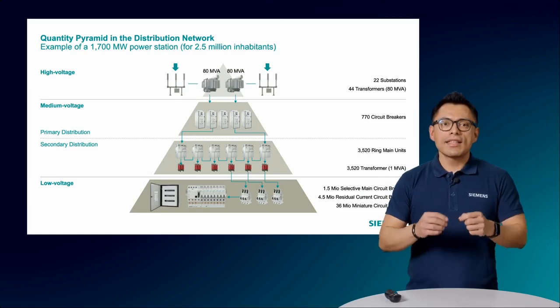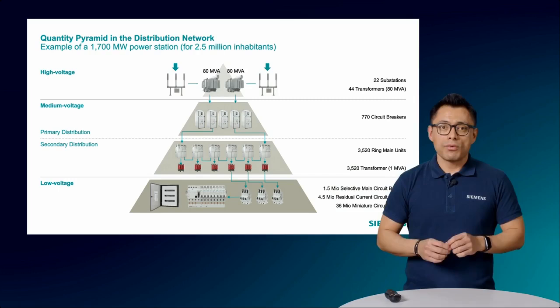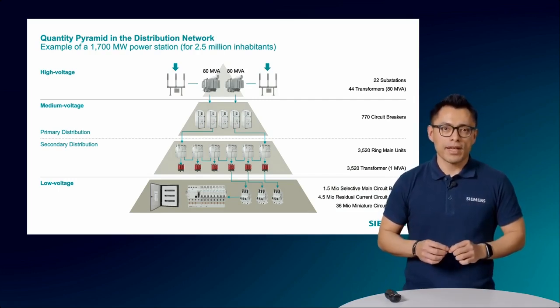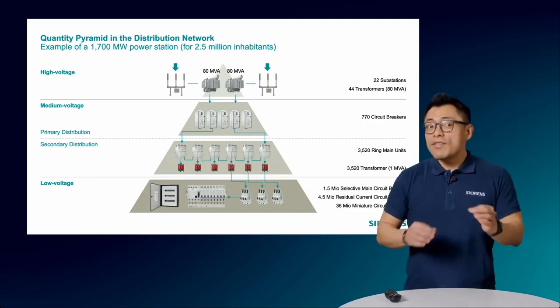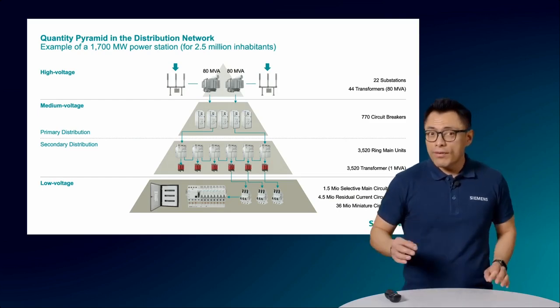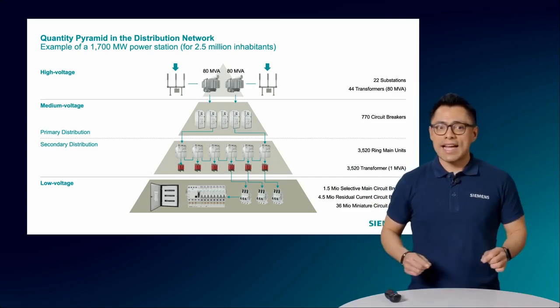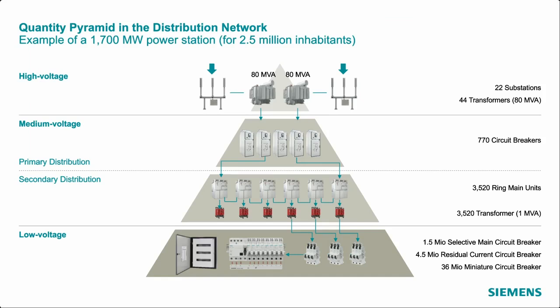Let's imagine this example. Let's say we have a city with roughly 2.5 million inhabitants, with a power demand of more than 1,700 megawatts. The design of the network involves several components. There is no rule regarding how many components are needed. However, as a general overview, we could say, from the top to the bottom, that at the top of the pyramid, we need to start with high voltage. For that, we will need 22 substations, each one of them with a capacity of 80 MVA to reach the total power demand. 44 transformers. Here, we can consider 2 transformers per substation, each one with a capacity of 80 MVA, but with a load of only 50% for security and reliability. The purpose of these transformers is to step down the voltage from high voltage, transmission, to medium voltage, distribution, and start the power distribution.